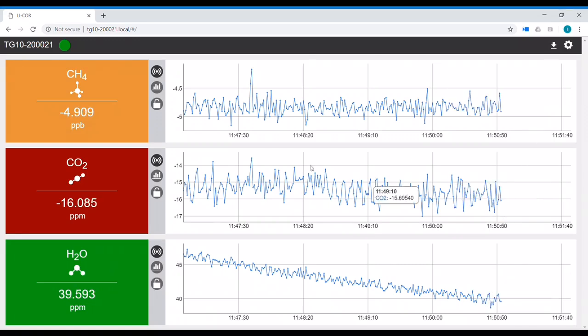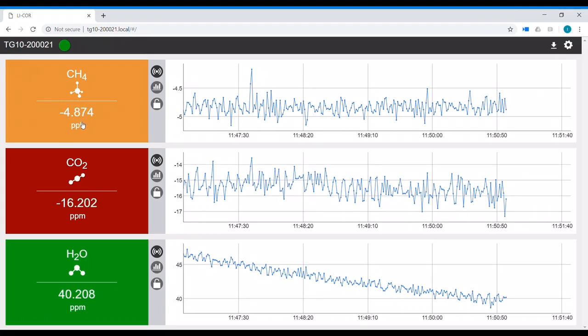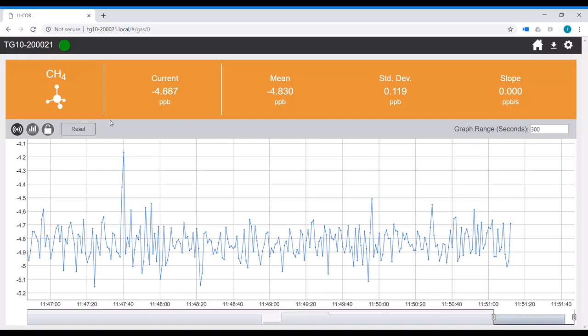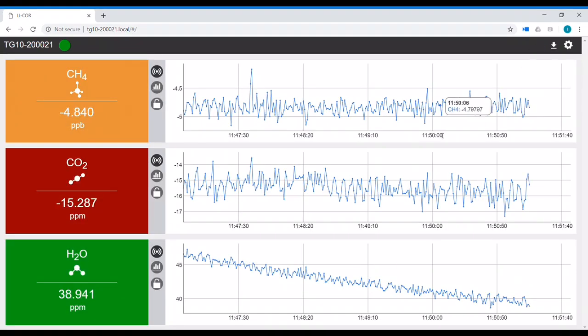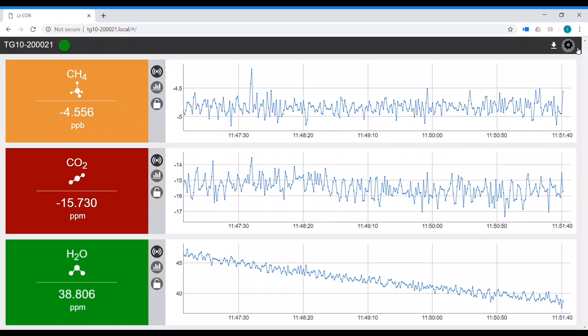One thing I would mention here, so right now we're looking at a downward offset of about -5 ppb on methane. It's not out of the norm to see that after several months of operation. But if you see, within a few weeks or within a few days, several ppb offset or several ppm offset on CO2, it may be that there's something else going on. Is the plumbing correct? Is there some leak, or is the instrument operating at the right conditions? Do you have all the indicators green on the status page or on the settings advanced page? So you want to make sure it's not an impact of the setup or something else before we conclude it's calibration drift and try to calibrate it out.